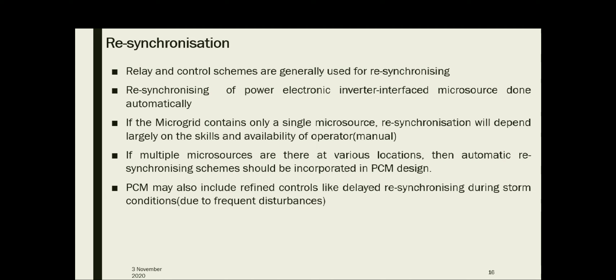The last scenario is resynchronization. Relay and control schemes are generally used for resynchronizing a conventional synchronous generator, either manually or automatically, and for automatically resynchronizing a power electronics inverter-interfaced microsource. If the microgrid contains only a single microsource, the choice of manual or automatic resynchronization will depend largely on the skills and availability of the operator. However, if multiple microsources are present at various locations in the microgrid, an automatic resynchronizing scheme should be incorporated.